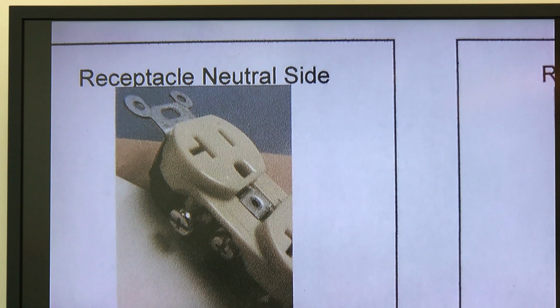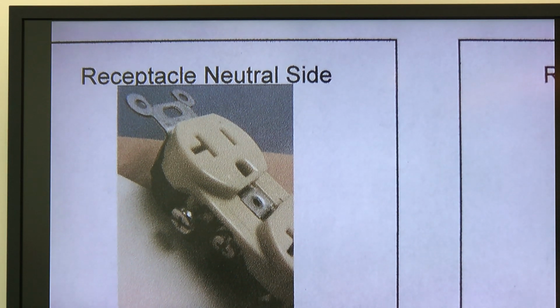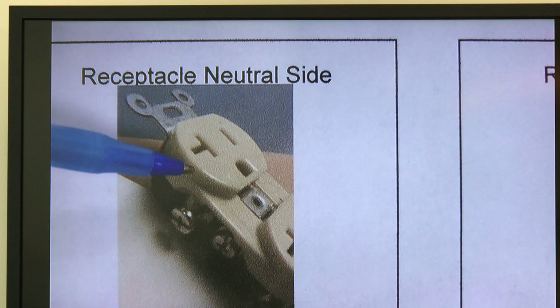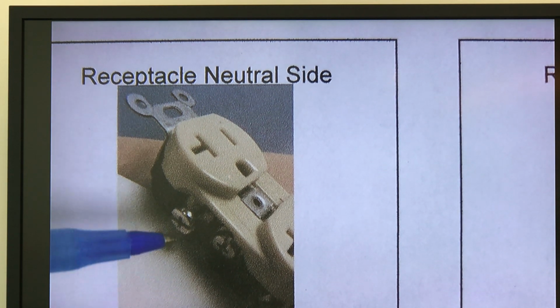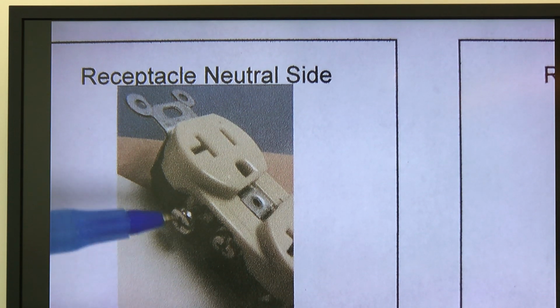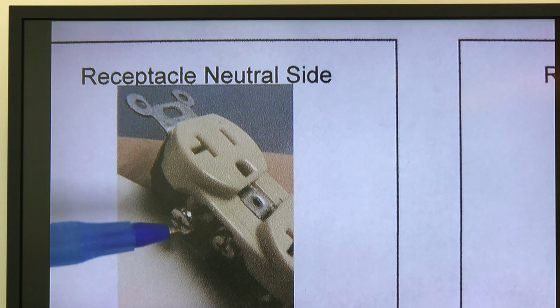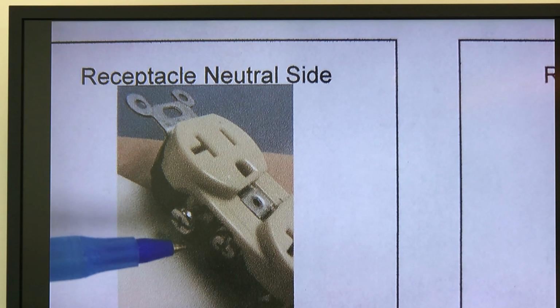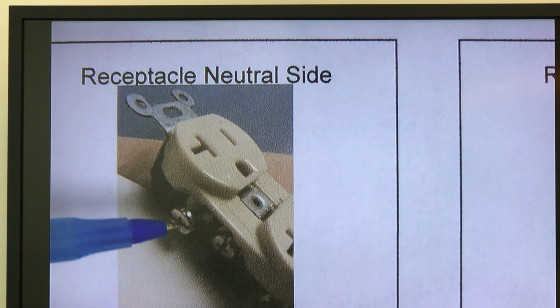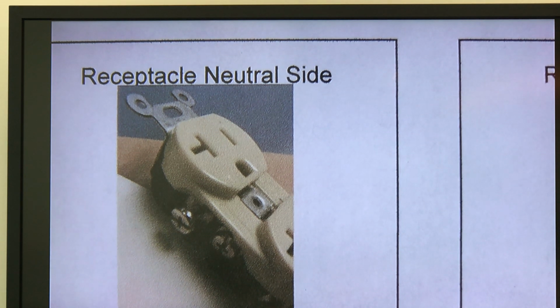Let's take a look at the side connections, because if you're inside an electrical panel, this is what you're going to be interested in. On the neutral side, here we have the neutral receptacle bus bar. Notice that this is silver, and these things just connect up. Most of them are arranged where you can either poke the wire into a small hole and there's a keeper mechanism, or depending on what you need to do with it, you can also twist or actually make a hook out of your connecting copper and put it under the screw.